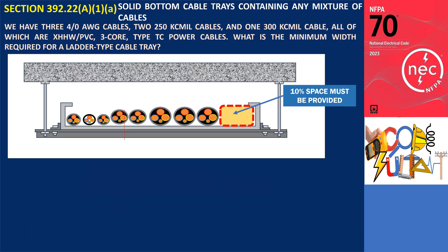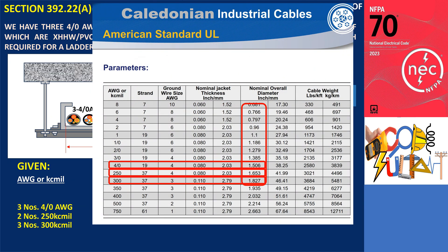For instance, we have three 4-aught AWG cables, two 250 kcmil cables, and one 300 kcmil cable, all of which are XHHW, PVC, 3-core, type TC power cables. What is the minimum width required for a solid-bottom type cable tray?